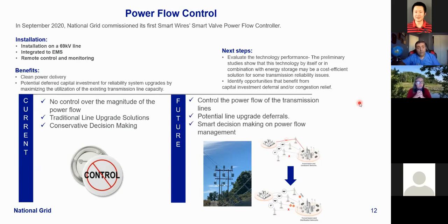Yeah, so the pilot is complete. We're in the process of working with ISO. We've presented some of our study results with 5% impedance compensation, which was a small number. Now we've moved up to larger scale in terms of study. Those studies with PSS/E studies for both dynamic and so on will be presented to ISO to demonstrate the benefits and performance of this device, and how fast it can go between different levels of impedance compensation, from capacitive to inductive and vice versa.